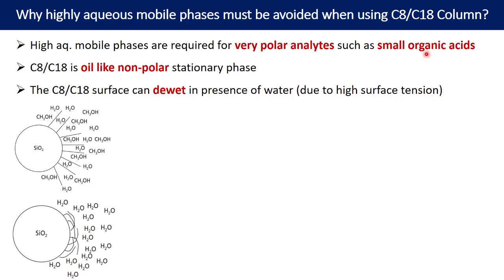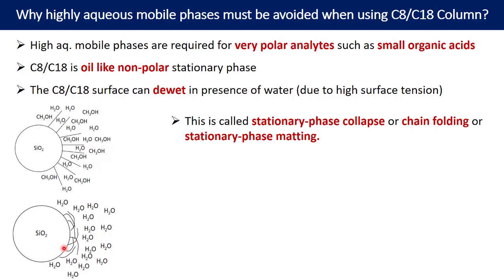Please look at these two important figures. In the first figure, the mobile phase contains water and methanol, and the bonded stationary phase like C8 or C18 is properly wetted. In the bottom diagram, there is no organic solvent — only aqueous mobile phase — and the bonded stationary phase is de-wetted. When de-wetting of the stationary phase happens, it is called stationary phase collapse, also known as chain folding or stationary phase matting.